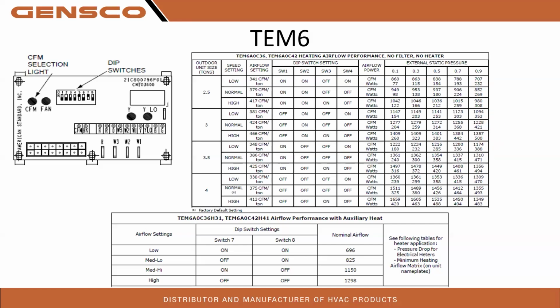If you hear of a homeowner complaining of high bills, they didn't have to pay this much on their old system, it could be their airflow is being restricted, therefore we're at higher static and we are using more, especially if they're running it 24/7. So when we first got variable speeds on the scene, the salesmen were saying, oh yeah, it'll overcome poor ductwork, but it'll only overcome slightly poor ductwork, and there is an additional cost to that for long run settings. So that's something you could have an open discussion with your homeowners about, on why they want to add that ductwork. So thank you, Mark, again.